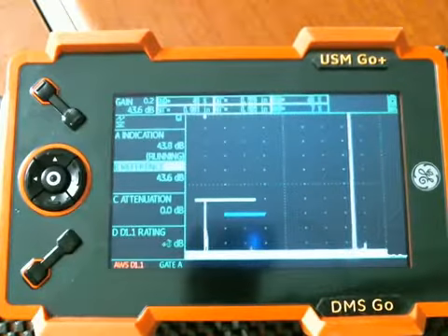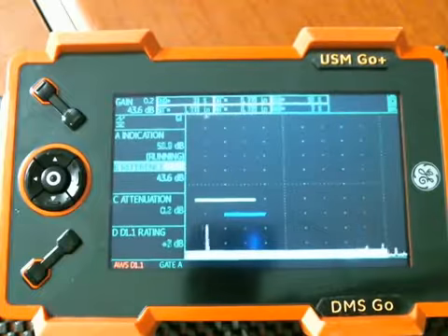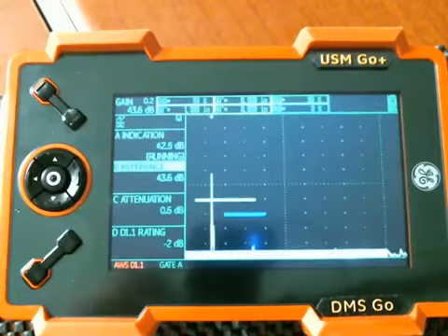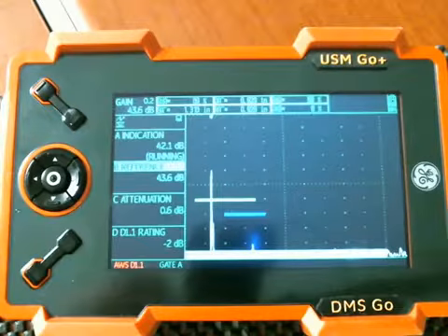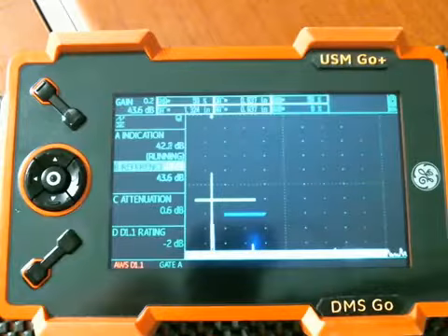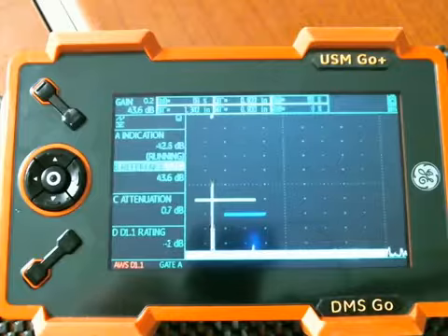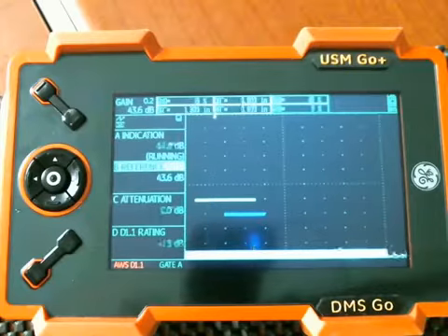So if I go out to a deeper hole, see, I actually can peak up a little more sensitivity on that. So it gives me some attenuation on the C factor to account for the greater depth. And it tells me that that hole's actually a little bit bigger or more to natural focus because it's coming up with greater sensitivity even though it's deeper.